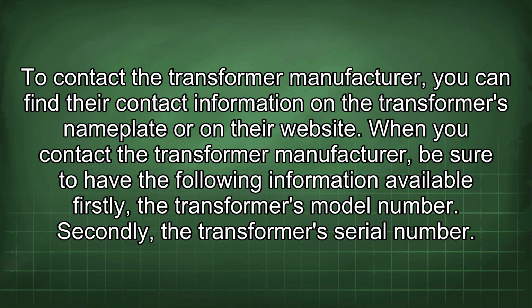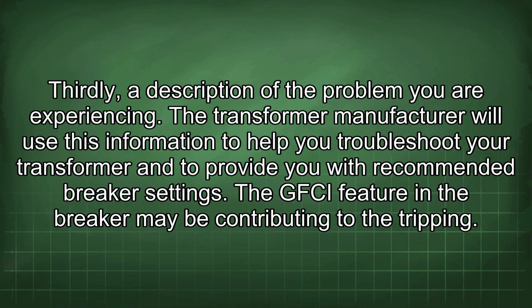Firstly, the transformer's model number. Secondly, the transformer serial number. Thirdly, a description of the problem you are experiencing. The transformer manufacturer will use this information to help you troubleshoot your transformer and to provide you with recommended breaker settings. The GFCI feature in the breaker may be contributing to the tripping.